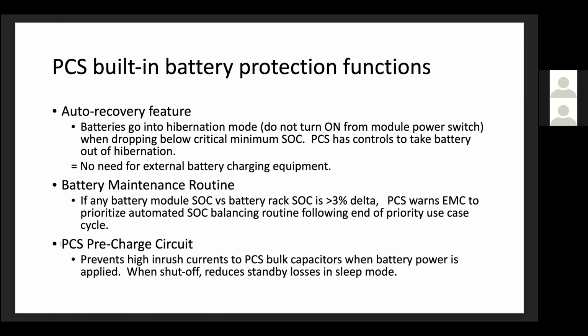Little note here on the PCS pre-charge circuit: just be informed that there is a pre-charge circuit within the inverter that prevents high inrush currents to the bulk capacitors whenever the battery power is applied. And when shut off, it reduces standby losses in sleep mode. So it's not really something that's required for installation, but just as a note, if you're turning a system off or on that's already running, there's a pre-charge circuit in there that you should be aware of. I think there's a note in the manual as well. If you turn the DC breaker off, wait a minute so that that pre-charge circuit can discharge before you turn it back on again.